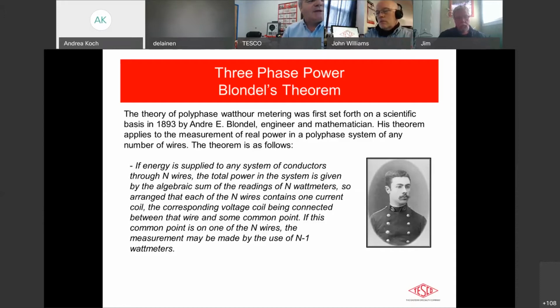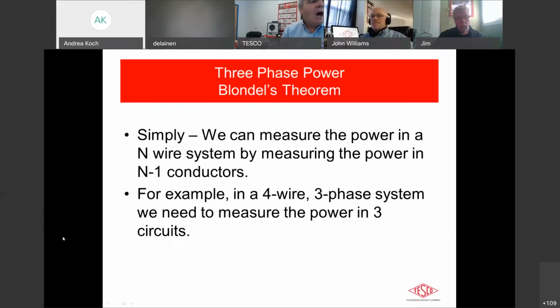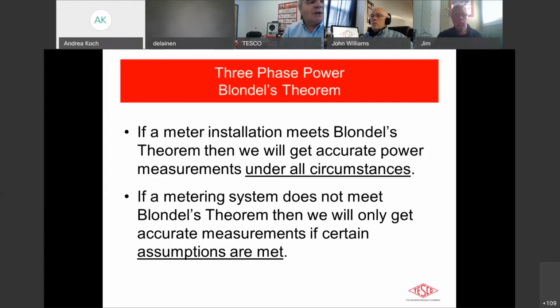you've got to basically have 2 watt meter measurements. Okay, there's a little more to it, but effectively you need 2 watt meters to accurately measure a 3-wire system. John, you want to skip on? Sure. So if you have 4 wires, you need 3 watt meters. Okay, that seems pretty basic. So what are some of the problems with this?